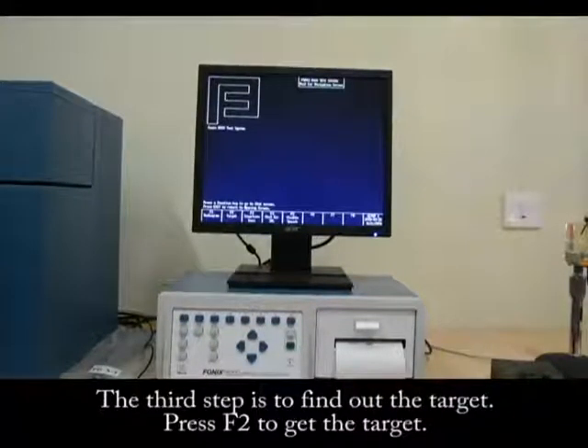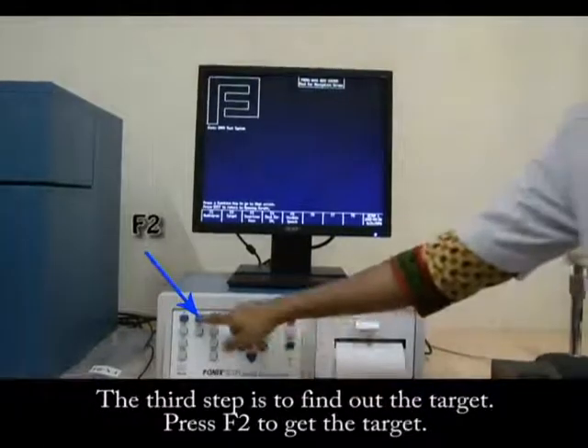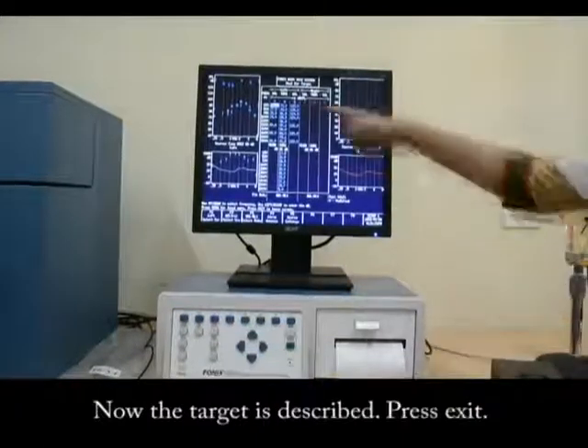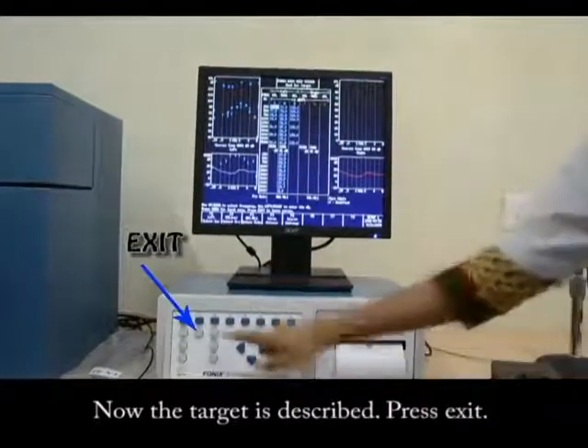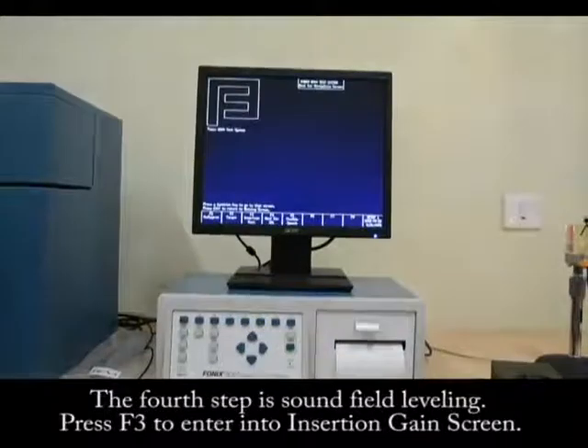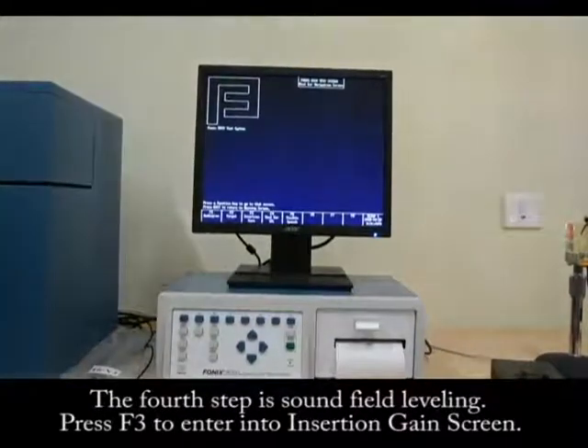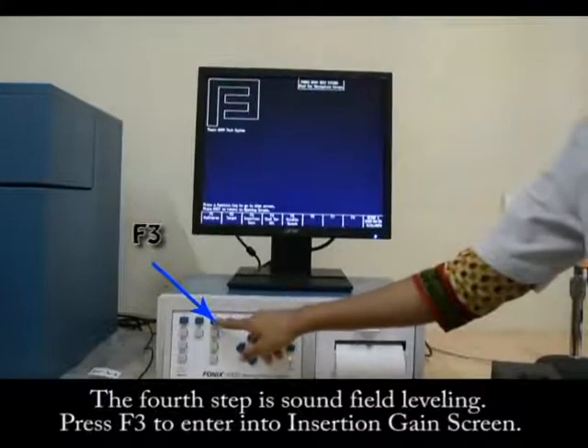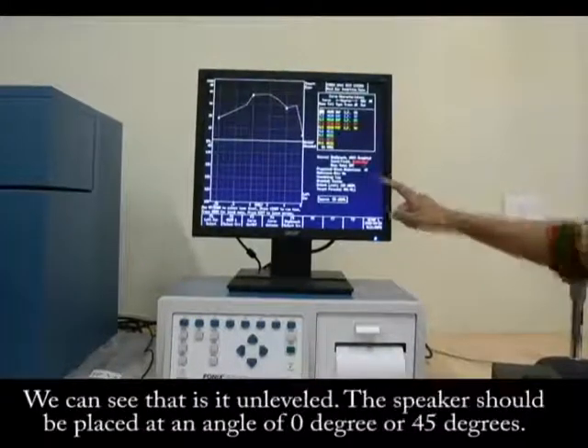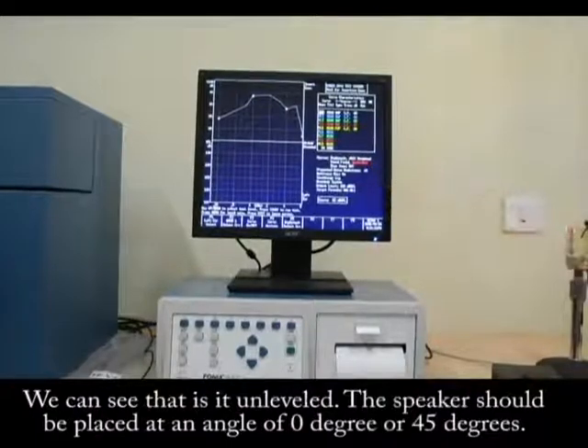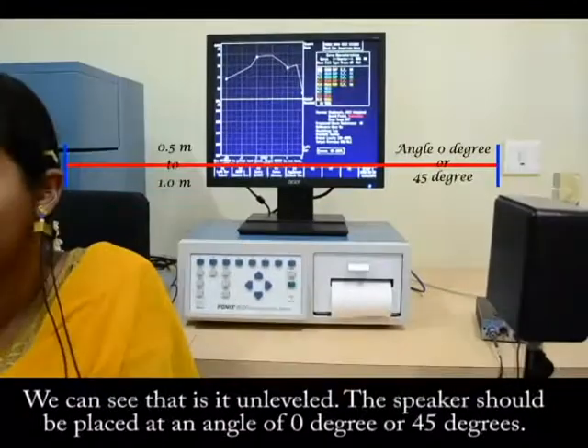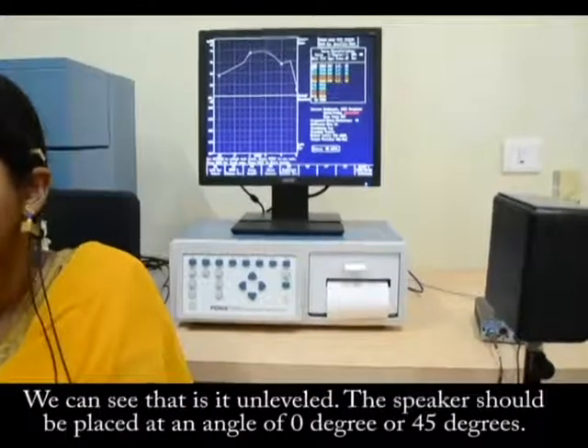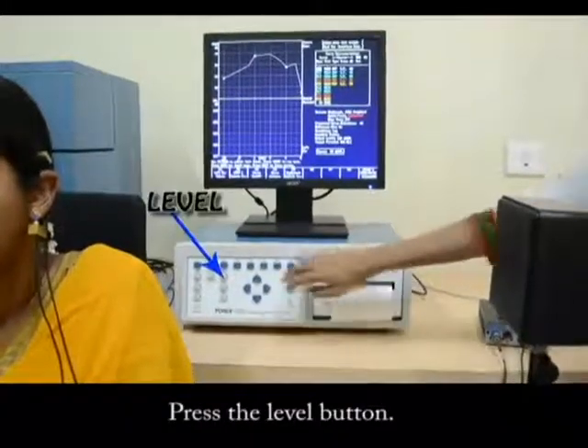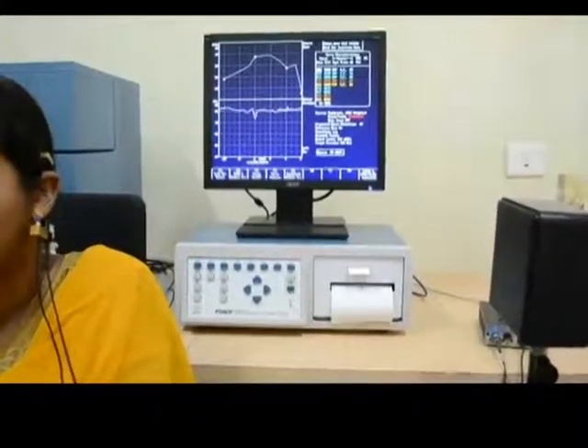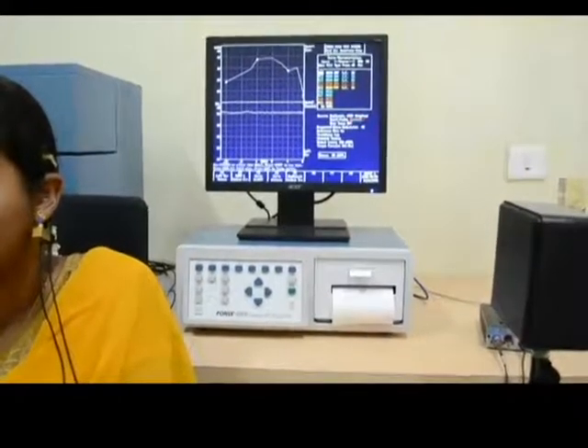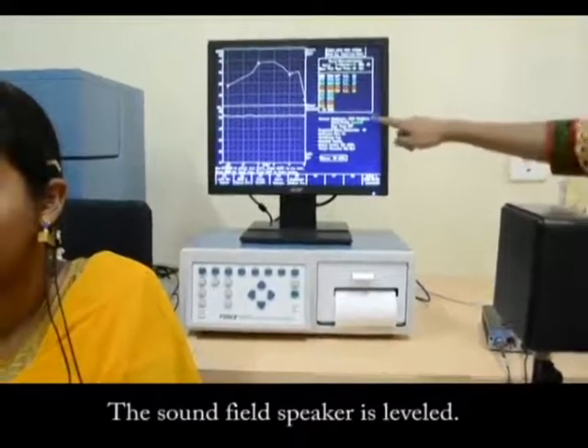The third step is to find out the target. Press F2 to get the target. Now the target is displayed. Press exit. The fourth step is sound field leveling. Press F3 to enter into the insertion gain screen. We can see that it is unleveled. The speaker should be placed at an angle of 0 degree or 45 degrees. Press the level button. The sound field speaker is leveled.